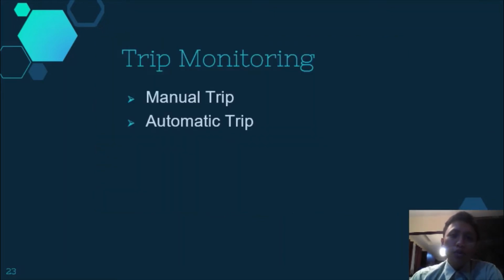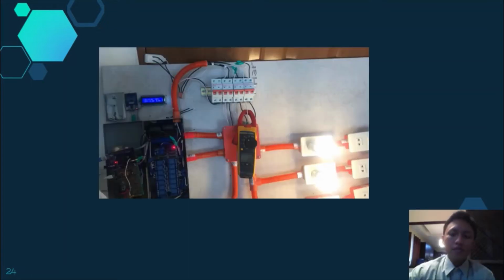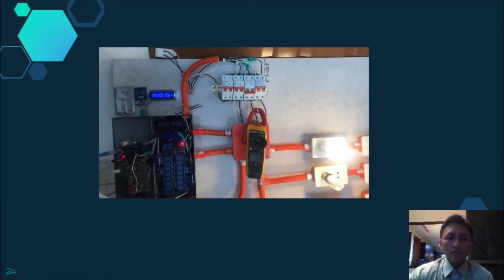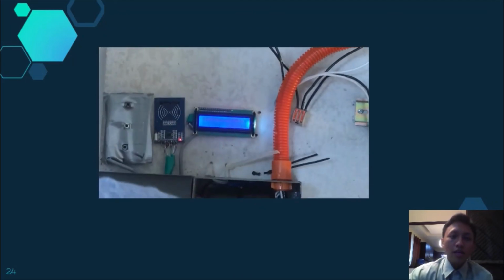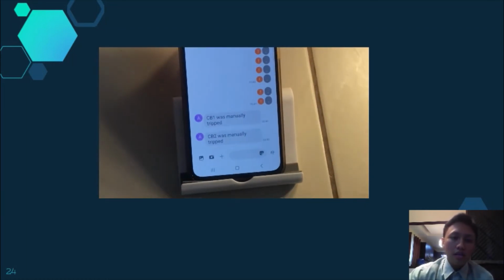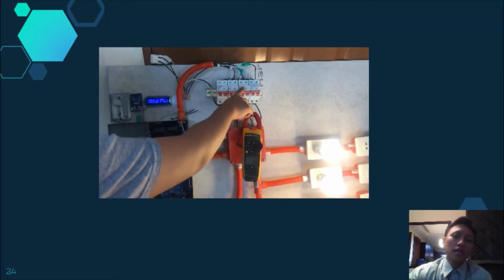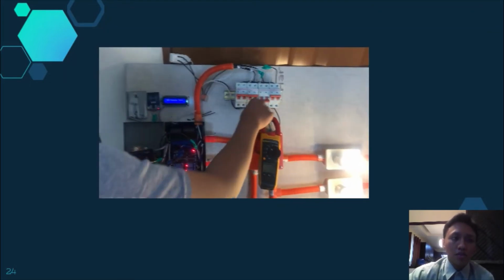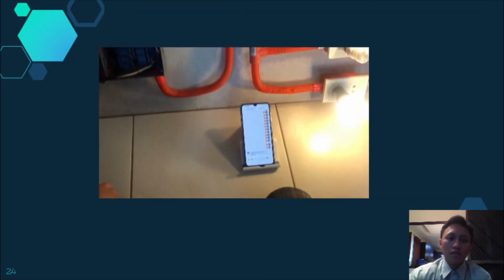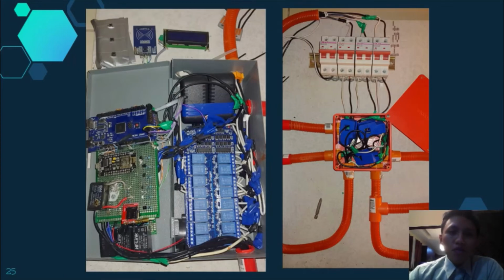To perform trip monitoring, by the way, trip monitoring refers to the system identifying what type of trip has occurred in the circuit breaker. It can either be manual trip or automatic trip. In this video, we'll be demonstrating how manual trip is detected and what the system response should be. So, as you can see, right after I turned off the circuit breaker, power is immediately cut off in the affected branch, and then a text message is sent to the user. As you may have seen in the previous video, we have turned off the circuit breaker, but after a few seconds, the power supply is restored to the load.